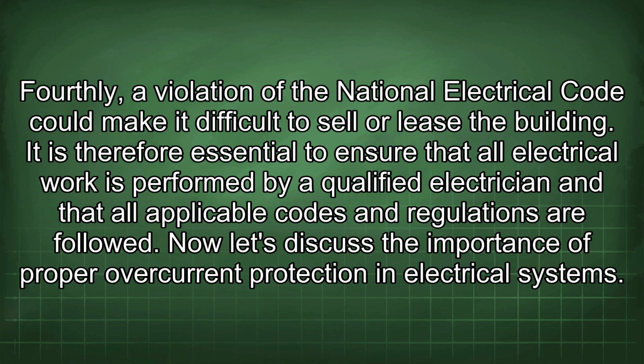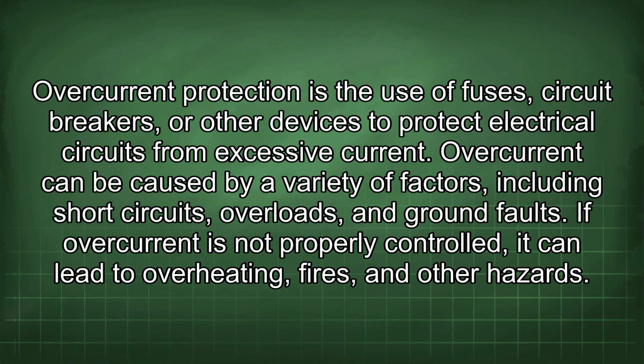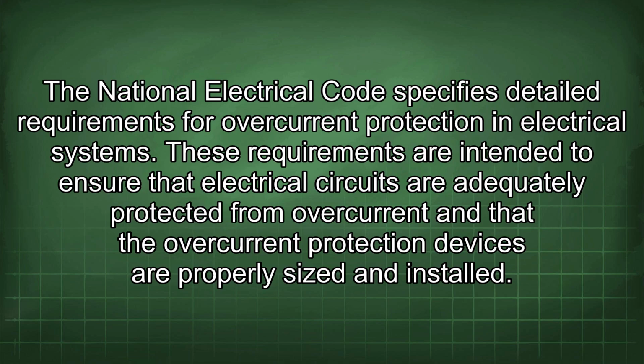Now let's discuss the importance of proper overcurrent protection in electrical systems. Overcurrent protection is the use of fuses, circuit breakers, or other devices to protect electrical circuits from excessive current. Overcurrent can be caused by a variety of factors, including short circuits, overloads, and ground faults. If overcurrent is not properly controlled, it can lead to overheating, fires, and other hazards. The National Electrical Code specifies detailed requirements for overcurrent protection in electrical systems. These requirements are intended to ensure that electrical circuits are adequately protected from overcurrent and that the overcurrent protection devices are properly sized and installed.